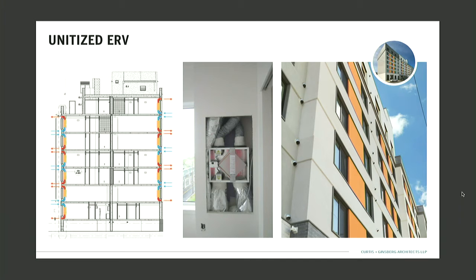So our first three buildings were the unitized system, and one of the ways we solve some of the issues that John's talking about is, here's our ERV, it's right in here next to the exterior wall. We exhaust high on one floor and low on the other floor. We still needed to go to the building department because the building department wants your supply and exhaust to be 10 feet apart. When you're doing a 9'4" floor to floor, that's hard without offsetting and so on. But all the manufacturers say you only need to be 5 feet apart. So we did this. We've done the determination now 3 times and gotten it all 3 times. And so this worked well.